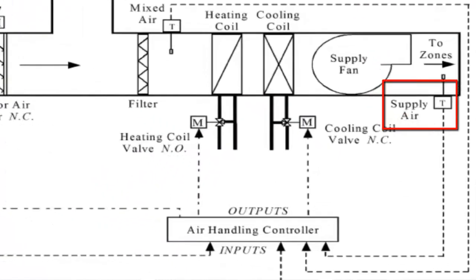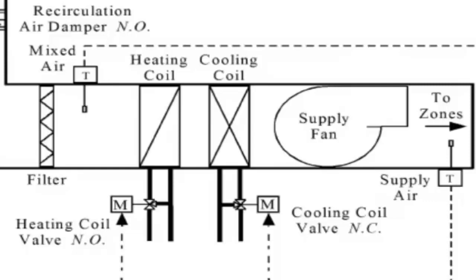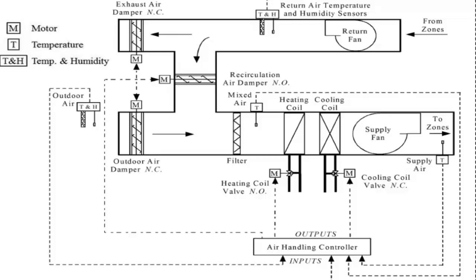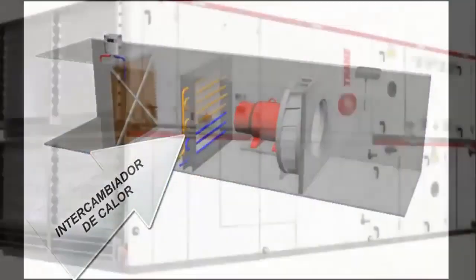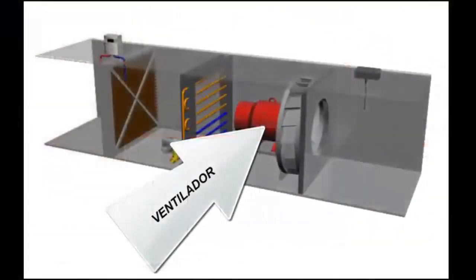Then we find heat exchangers to reach the appropriate temperatures. The supply air is measured as it leaves the air handling unit, and is compared with the set point. In the heat exchangers, there is a hot or cold fluid, usually water, or perhaps steam.